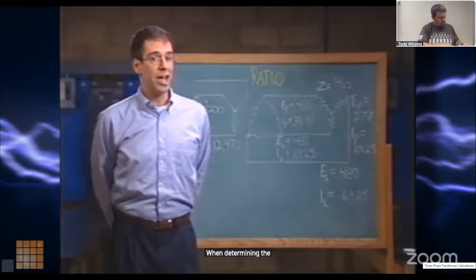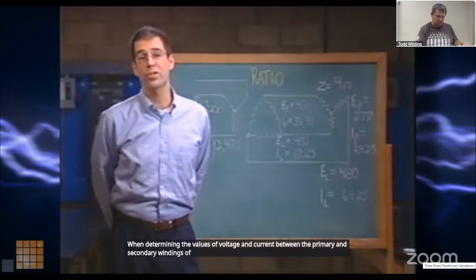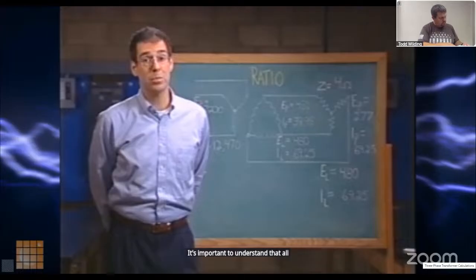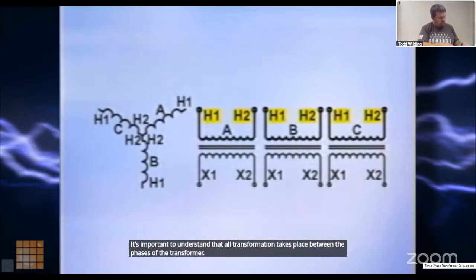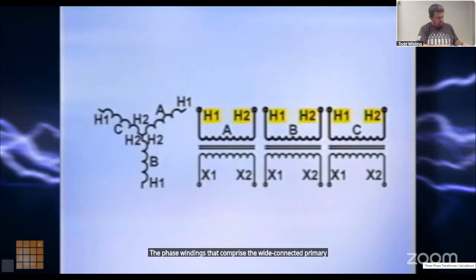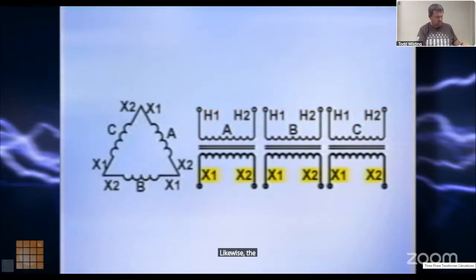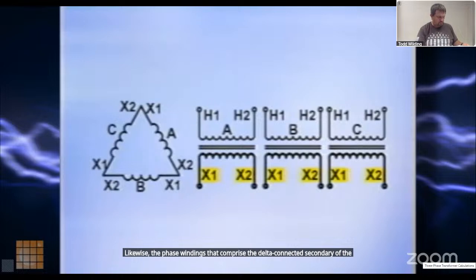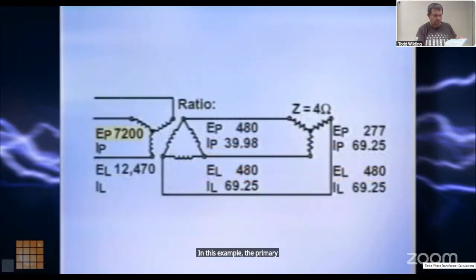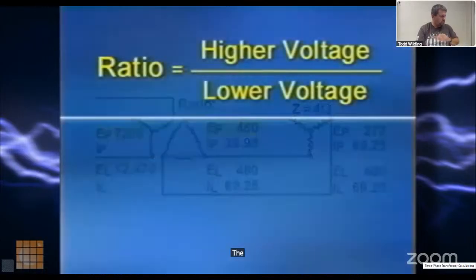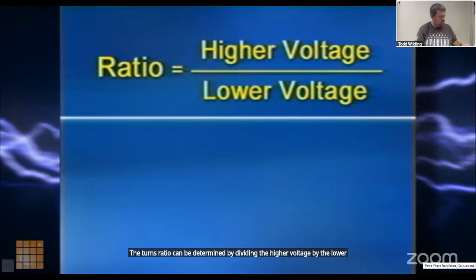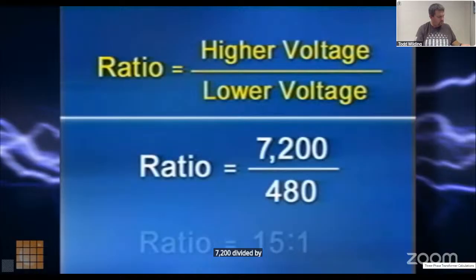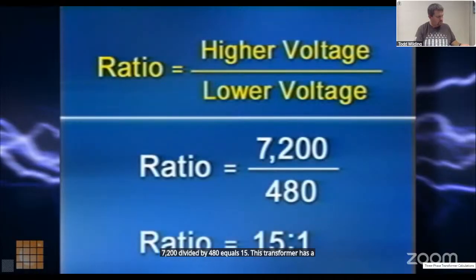When determining the values of voltage and current between the primary and secondary windings of a three-phase transformer, it's important to understand that all transformation takes place between the phases of the transformer. The phase windings that comprise the Y-connected primary of the three-phase transformer bank are the high-voltage windings of the three single-phase transformers. Likewise, the phase windings that comprise the delta-connected secondary are the low-voltage windings of the three single-phase transformers. In this example, the primary has a phase voltage of 7,200 volts, and the secondary has a phase voltage of 480 volts. The turns ratio can be determined by dividing the higher voltage by the lower voltage. 7,200 divided by 480 equals 15. This transformer has a turns ratio of 15 to 1.